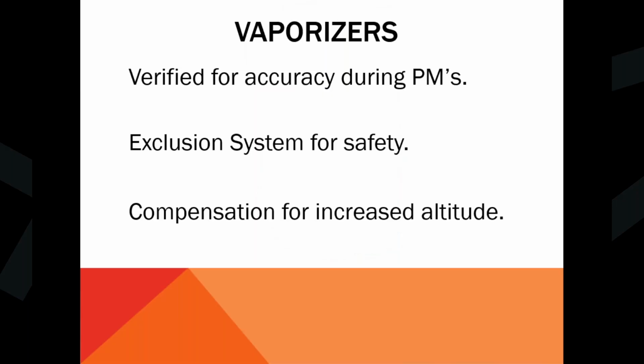Some of the things that you might do with the vaporizer during a PM: you want to measure the accuracy. So if you're setting it at 4%, you're going to want to see 4% plus or minus some percentage. And then there's also an exclusion system for safety. Most of the vaporizers have their own built-in exclusion system. What the exclusion system does is, if you have more than one vaporizer on the machine, the one you have turned on will lock out the other vaporizers. So you can't turn on two vaporizers at the same time. That's one of the things you'll want to check during your PM.